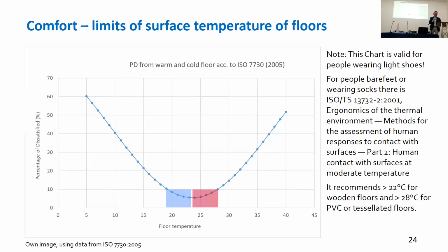But if we change the view and go to the floor and ask ourselves how hard could we cool the floor, then we come to the contact temperature. This is what ISO 7730 tells us. They say people start complaining when the floor gets lower than 18 degrees or warmer than 27 degrees. I'm concerned about this 18, but Ole Fanger did his research with people wearing light shoes. He did not do his research with people wearing socks or nothing. He did it with people wearing shoes. So this 18 degrees floor temperature, I think it's dangerous if applied to modern people running around with socks or something less in their flats.